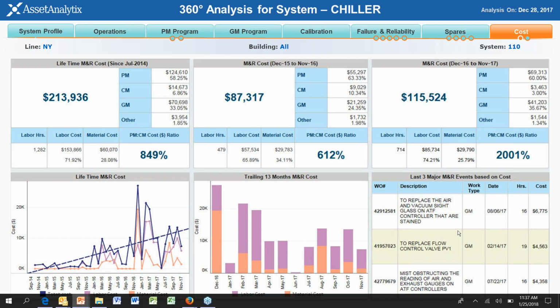There is an ISO standard around some of these failure codes, but really I would leave it to how you are addressing the PM program, and rely more on that, because the data can be aligned for proper analysis if your failure modes are addressed as part of your PMs.